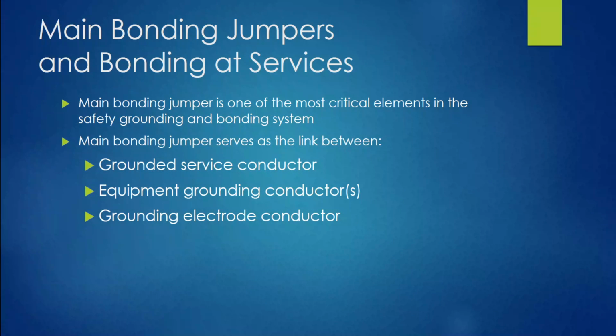Now, there are some allowances if you're going to use a wire-type main bonding jumper to connect to, let's say, another equipment grounding terminal bus, and you connect the two together, where that equipment grounding conductor terminal bus is connected to the enclosure, and now you're just trying to make those connections back to the grounded conductor, which is required by the code. That jumper, if of the wire type, has to be sized as a main bonding jumper in accordance with 250.28(D). We'll look at all that as we get into more of the presentation.